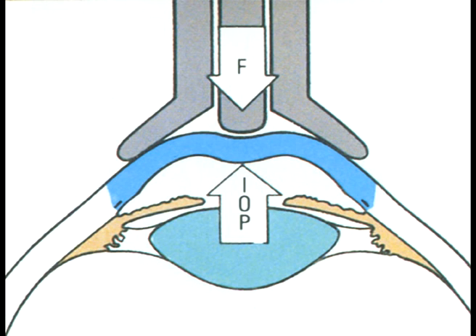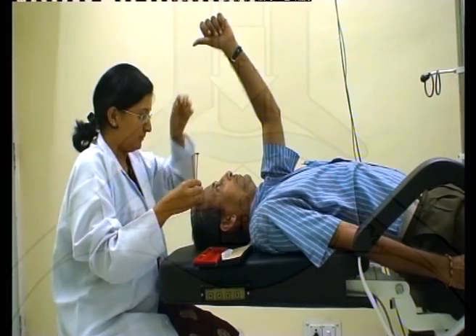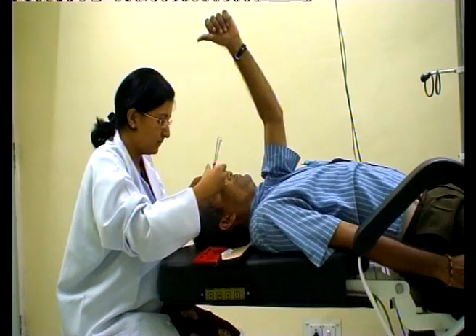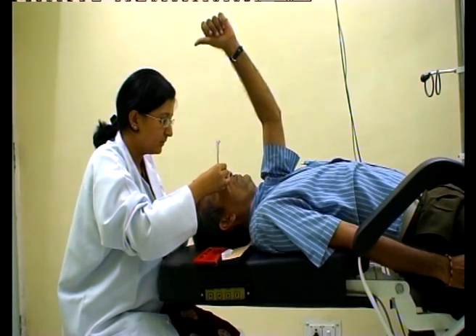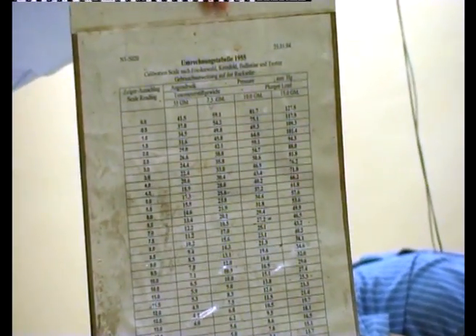Schiotz's tonometer displaces a large volume of fluid and hence scleral rigidity affects results significantly. As a result, the amount of fluid displaced is variable and unpredictable, which gives inconsistent results and hence requires conversion tables based on empirical data. In applanation tonometry, the shape of deformation is simple flattening and is constant. Therefore, the relationship of intraocular pressure can be derived from mathematical calculations.